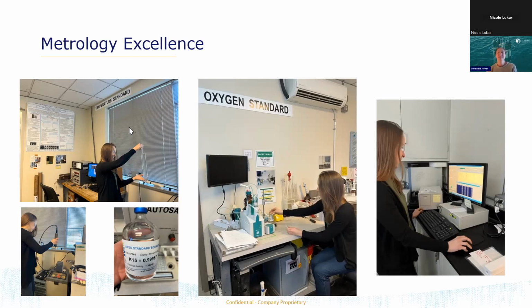And what we use is a transfer standard. And so we use a platinum resistance thermometer. And platinum is a great metal because it has a very linear temperature response. So we have these two pins, these 2 points that we've pinned the temperature at. We've created those temperatures, so we know that those are real. And then we use this platinum resistance thermometer to interpolate and extrapolate to get to that full ocean range that we're looking at measuring. The only problem with a platinum resistance thermometer is that it is very delicate.